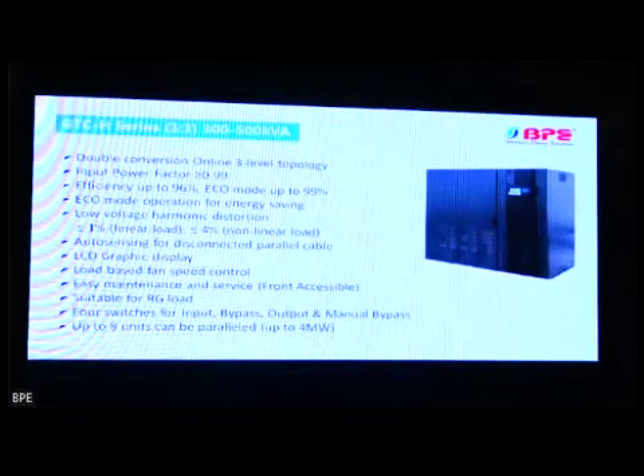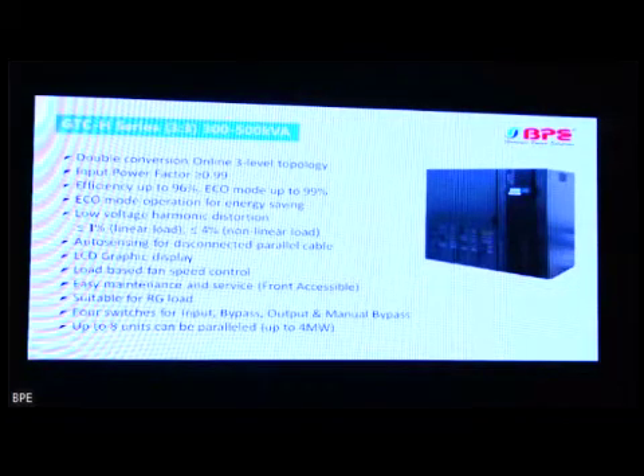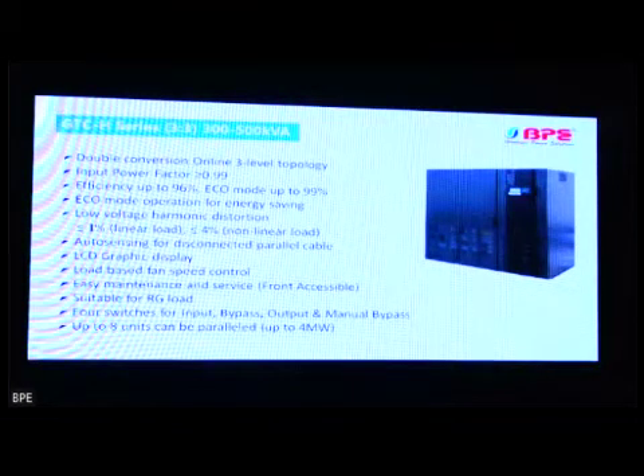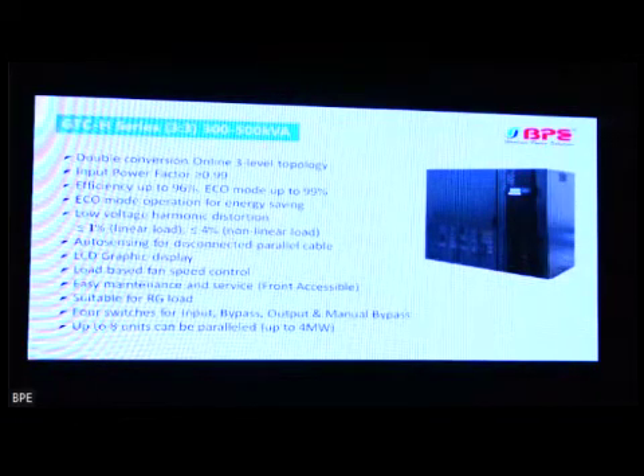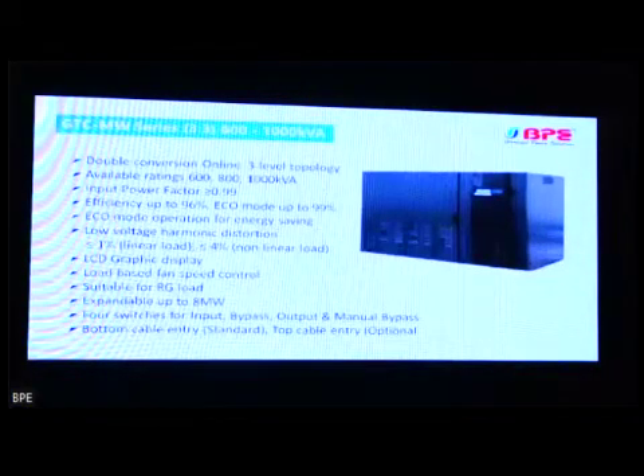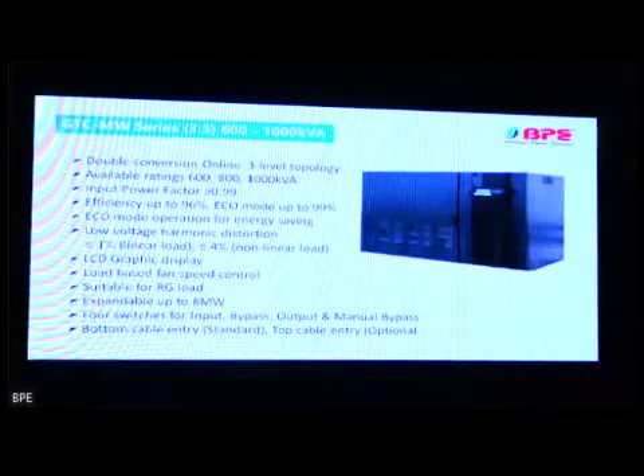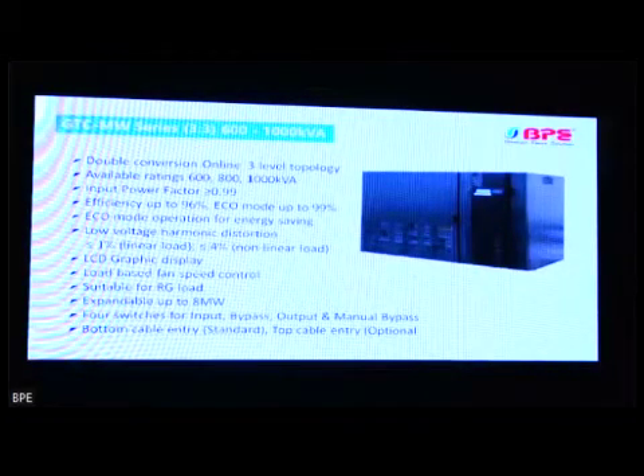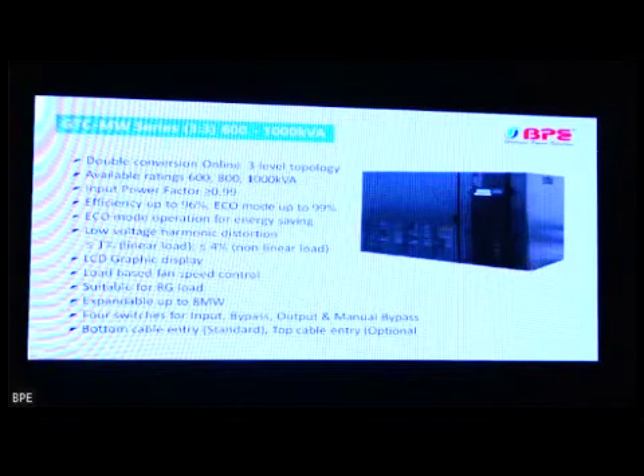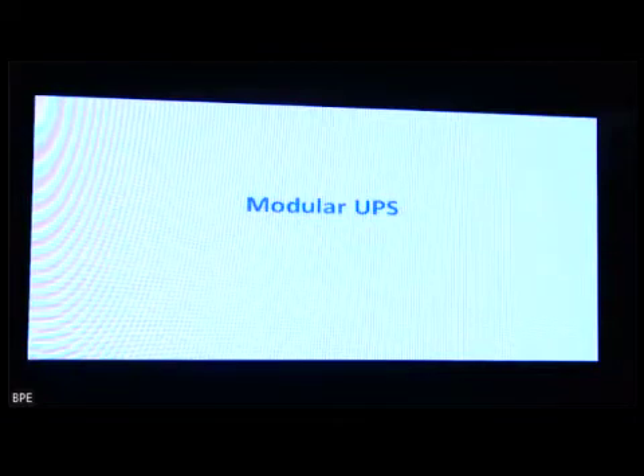There is an LCD graphic display, and it has also got a load-based fan speed. So when the load is less, the fan speed reduces to increase the efficiency, because it will save power. And this is suitable for regenerative kind of load. 4 switches are there, and we can go up to 4 megawatt by adding multiple UPSs. Then we have the GTC megawatt series up to 1000 kVA, and this series can go up to 8, so you can give a solution with this up to 8 megawatts.